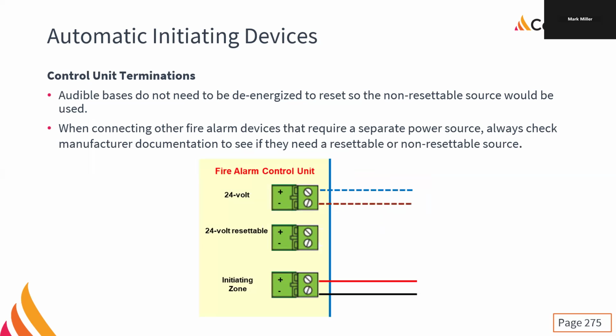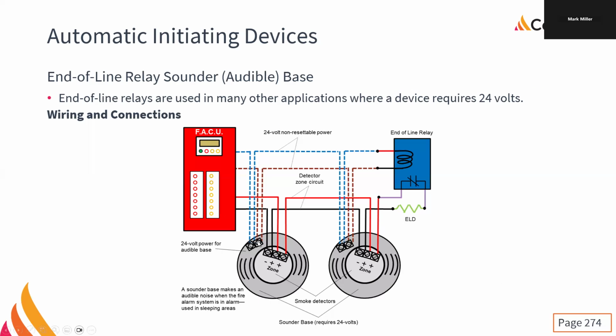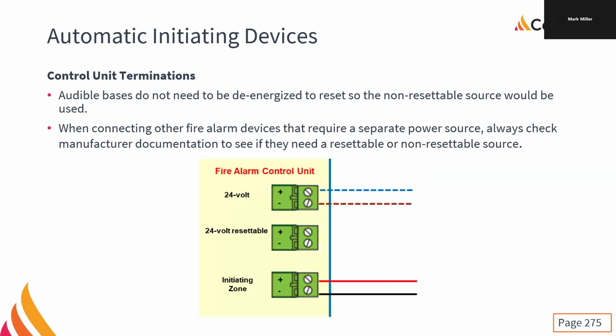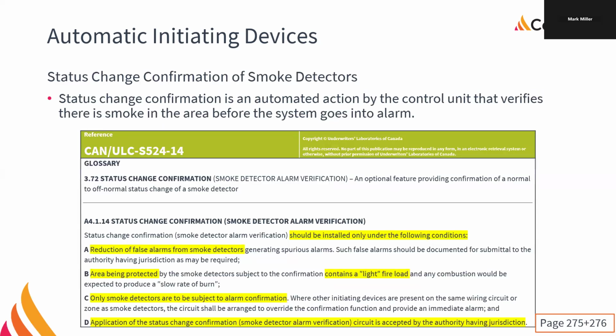The audible bases do not need to be de-energized to reset. So we use the non-resettable source because the smoke detector itself is pulling power from the zone just like a normal smoke detector does. We've got to be careful with that though, because certain manufacturers' sounder bases require resettable power. Certain manufacturers' sounder bases require non-resettable power. It varies by manufacturer on how they're accomplishing it. So always check the documentation so that you're terminating it properly.